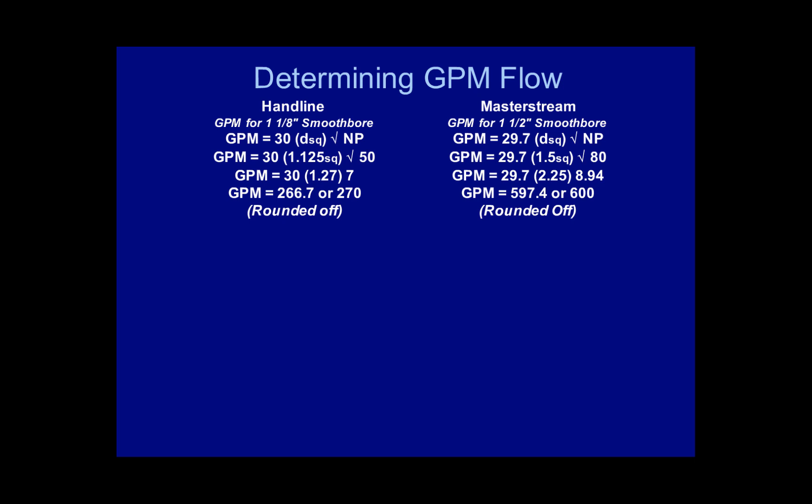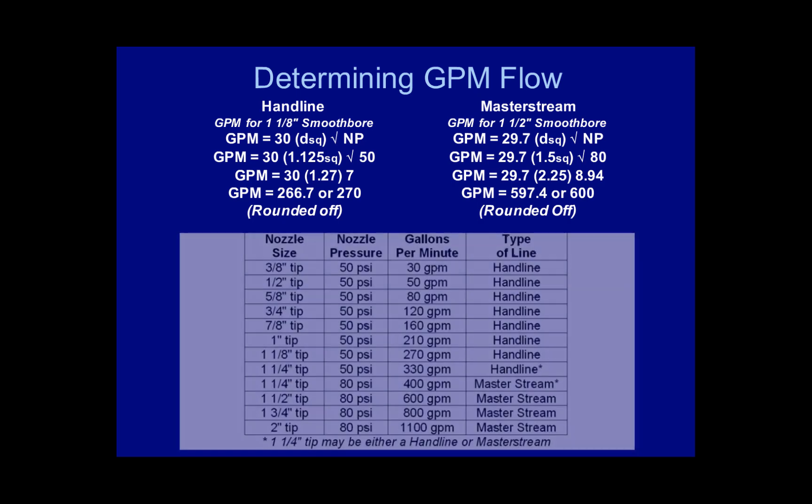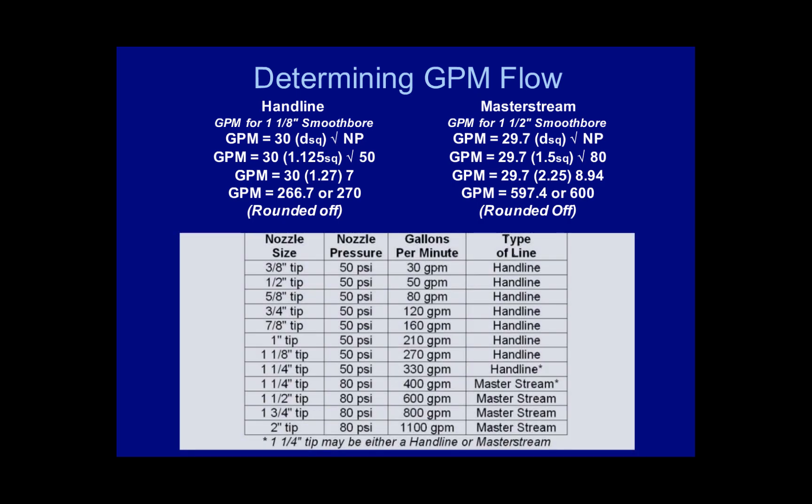Let's look at a master stream appliance and determine the GPM for an inch and a half smoothbore tip. We will use the more precise formula: GPM equals 29.7 times diameter squared times the square root of the nozzle pressure. GPM equals 29.7 times 1.5 squared times the square root of 80 for a master stream, equaling 29.7 times 2.25 times 8.94, which equals 597.4, or rounded off to 600 GPM. A table is provided to illustrate GPM flows for a variety of tips; note that an inch and a quarter tip can be used as either a handline or a master stream.